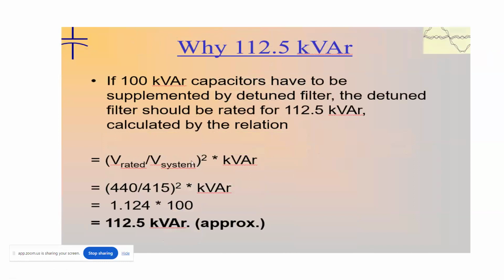There is one more important point regarding the filter. When we plan to have a capacitor, say a 100 kVAR capacitor, capacitors come in three voltages: 440 volt, 480 volt, and 525 volt. The capacitor should always be heavy duty. Why? Because if we have a detuned reactor, a detuned filter, before the capacitor, then due to the detuned filter the voltage at the capacitor will increase. If we place a 440 volt capacitor along with a detuned reactor, due to the high voltage the capacitor will fail. That is why the capacitor should always be of higher voltage, like 525 volt, which we have to plan.